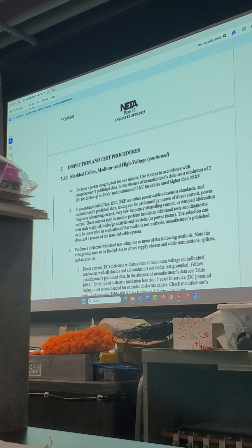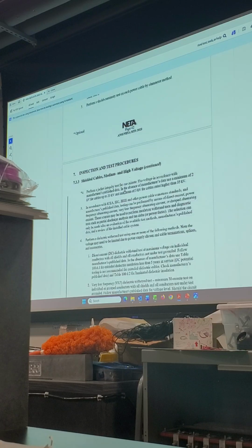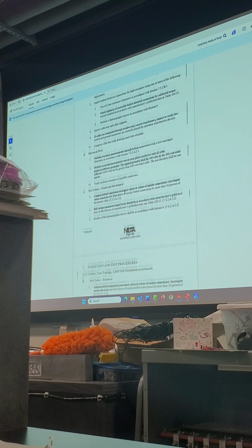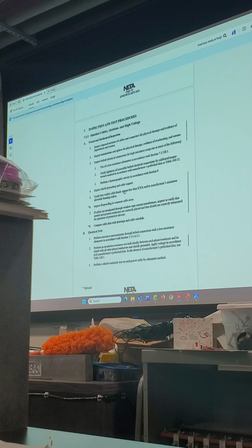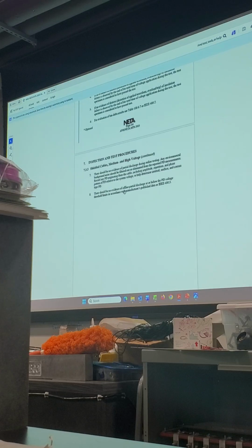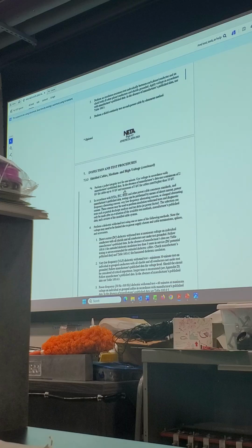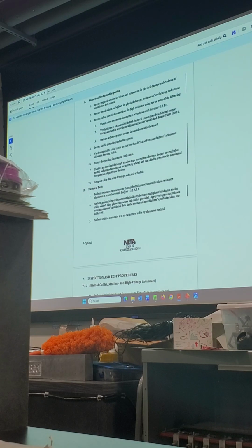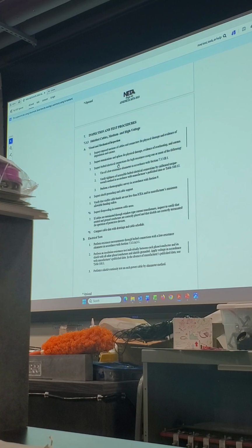So what we can tell is especially - just over one page was our low voltage cable, but by the time you get to a medium high voltage cable, we're looking at one, two, three and change, into the fourth page. So as equipment gets bigger, as transformers get bigger, as circuit breakers get bigger, there will understandably be a lot more testing to be performed in order to understand the full extent of the equipment. Especially at high voltages when things are much more critical and can get a little iffy, we definitely want to test it in more ways with more complex testing methods.